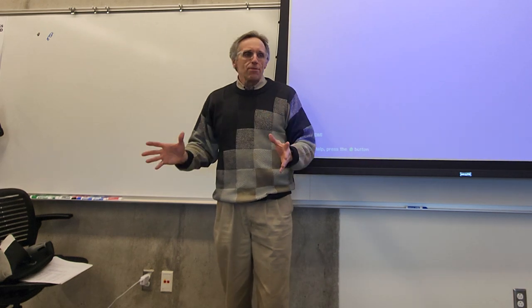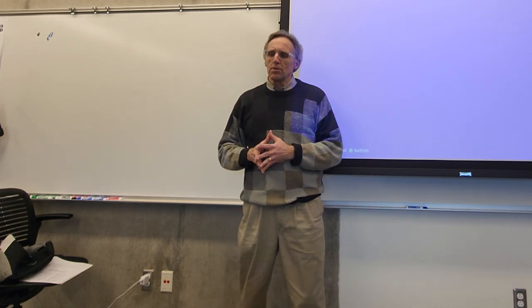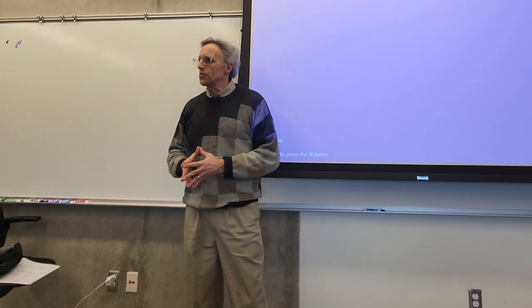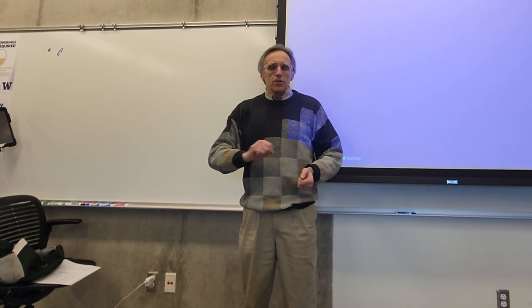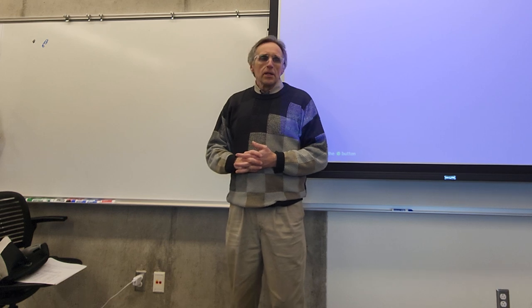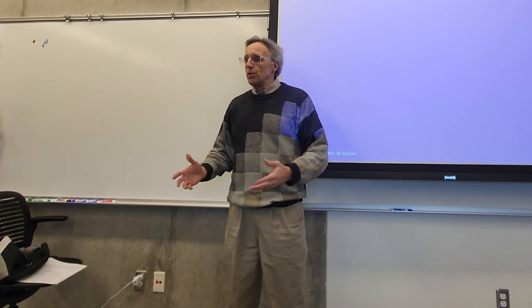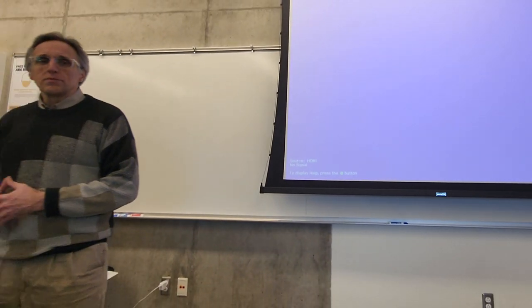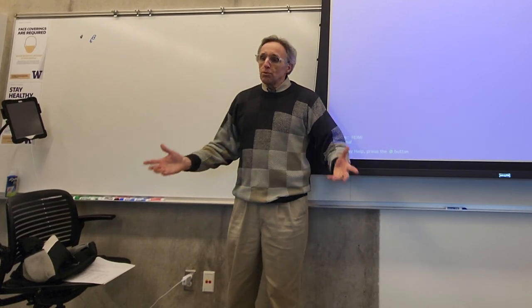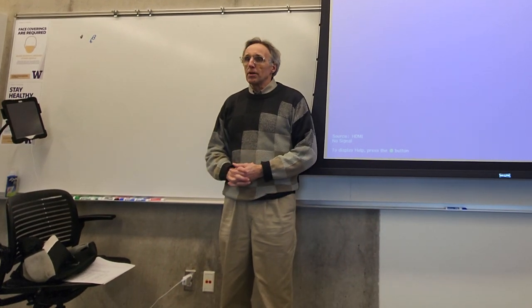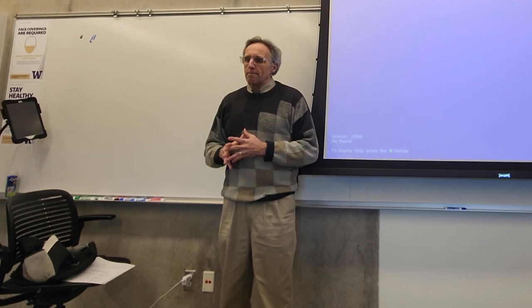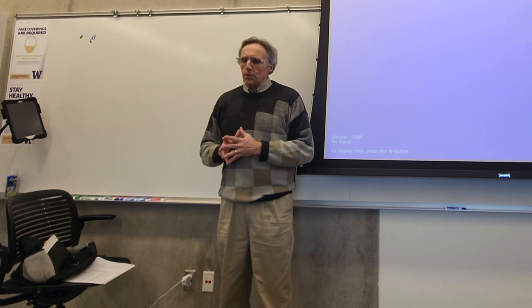a simplified method. And actually, that's what we're going to look at, is this simplified method called the cooling load temperature difference method. It's the old-fashioned way of doing stuff by hand, from before you had computers, and now that we have computers, it's a rough, quick and dirty calculation of loads. But we can do some simple stuff. We can do hand calculations for relatively simple buildings for winter time. It's not too bad. It's really the summertime that we really run into trouble.